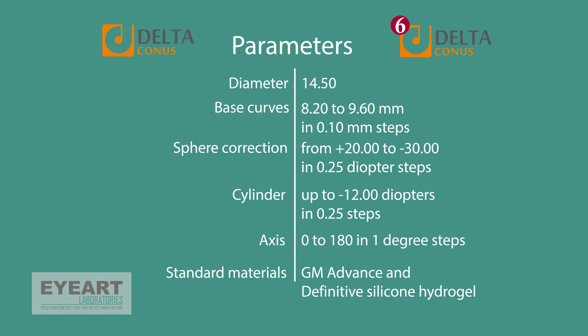Delta Conus have a diameter of 14.5 mm and base curves from 8.2 to 9.6 mm in 0.1 steps. The sphere correction range is between minus 30 to plus 20 diopters, cylinder correction up to minus 12 diopters in 0.25 steps, and axis in 1 degree steps. Standard materials are GM Advance with 49% water content and Definitive silicone hydrogel with Dk of 60 and modulus of 0.39. More details can be downloaded from www.eyeart.org, and additional parameters or material options are available on request.